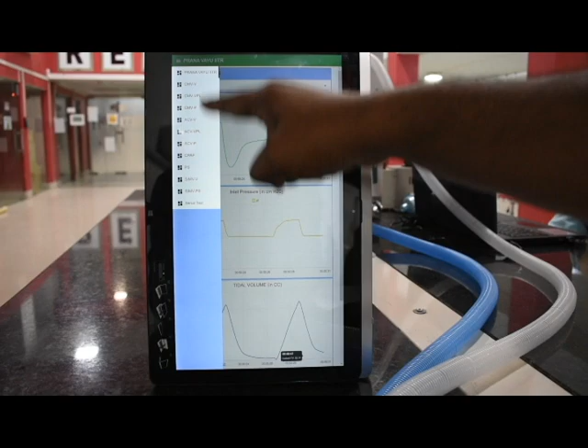Thank you, Professor Das, for a wonderful demonstration. Now, coming to the most important part of this demonstration: the ventilator Pranvayu has multiple safety features, and these features are more or less in line with the regulatory standards. We have primarily four alarms. The first alarm is with respect to the pressure range. If pressure exceeds a particular value or is lower than a particular value, the alarm triggers automatically.